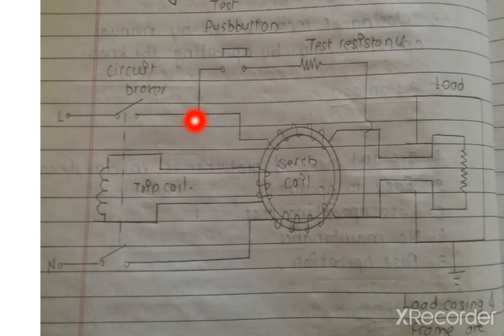The live contact is further connected to the load and then to the search coil. The high series test resistance is connected between the live and neutral terminal. This is connected with the push button. This is it for the construction point of view of the earth leakage circuit breaker.